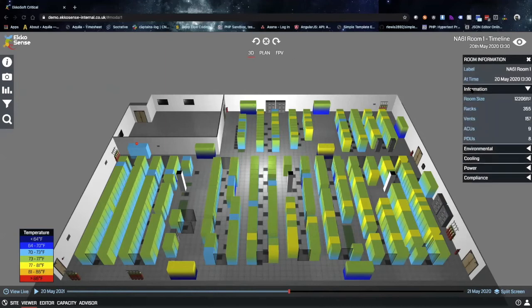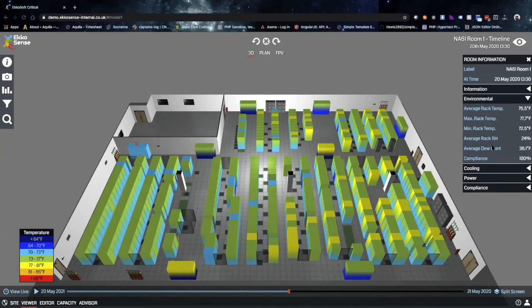So as you can see, we can see just some general information: the room size, so the square footage of the room, how many racks are in this room, vents, which are supply tiles, ACU units, as well as PDUs. Then we can go and see some environmental information, which is showing a lot of the same information you saw on the first screen there, which is the average rack temperature, the max temperature and the min temperatures, the relative humidity, dew point, as well as compliance level.